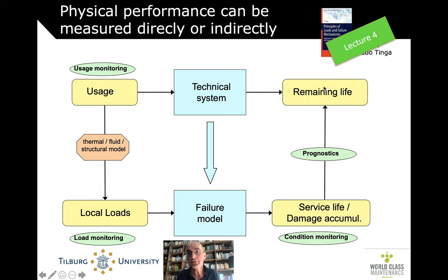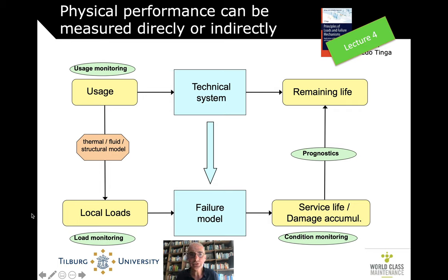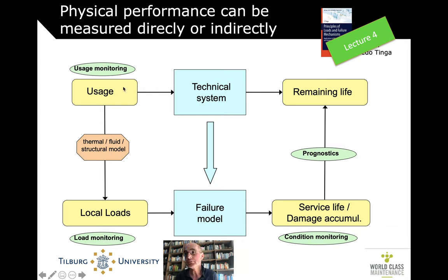In the end, you want to know how long will this asset still remain in sufficient condition. You can directly measure its actual technical condition, but you can also indirectly measure what over time will generate that condition — what will drive it forward, which is the load on the system. And the load on the system you can measure indirectly again by observing what the system is doing: its usage.